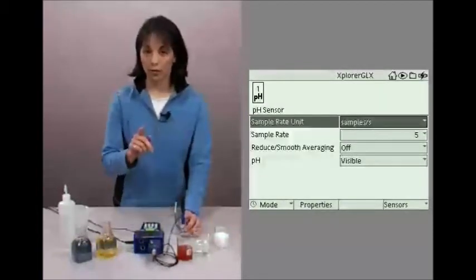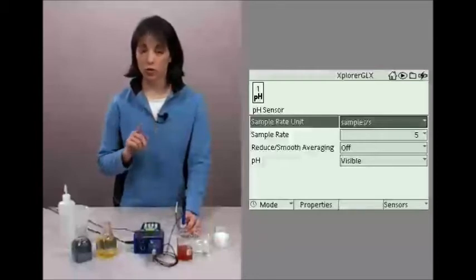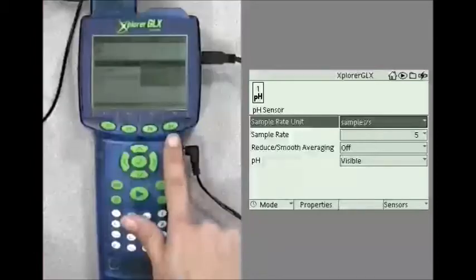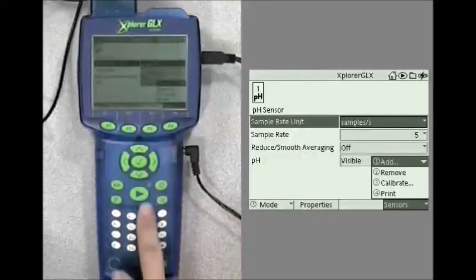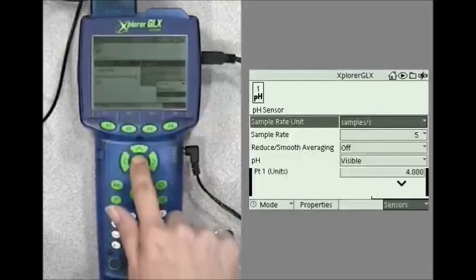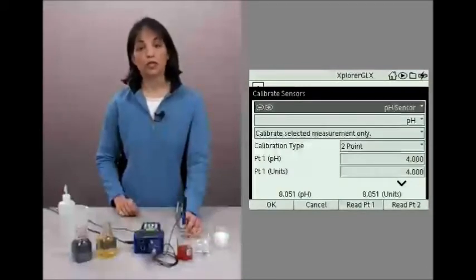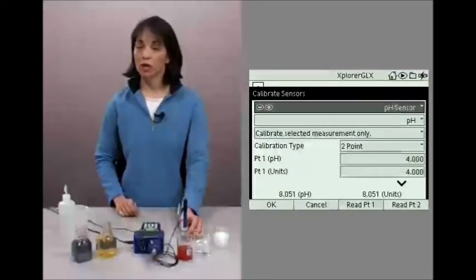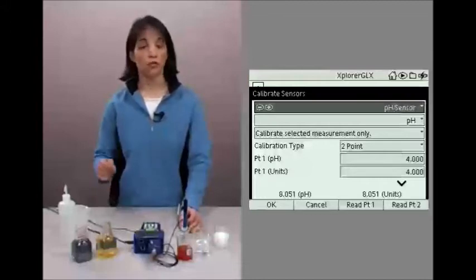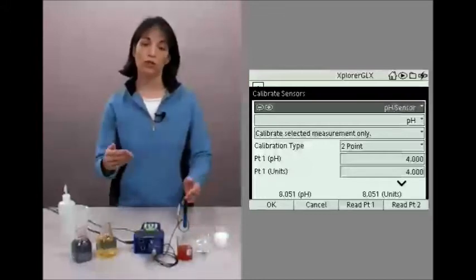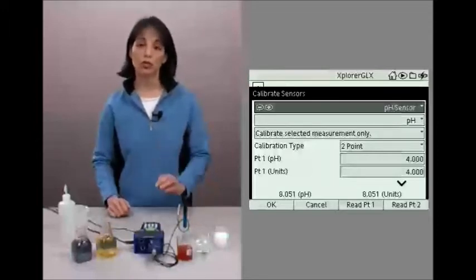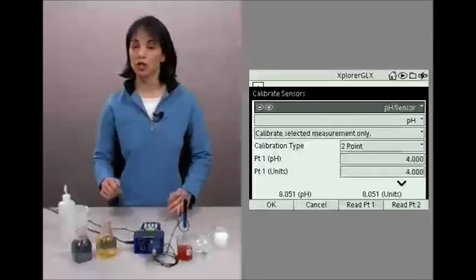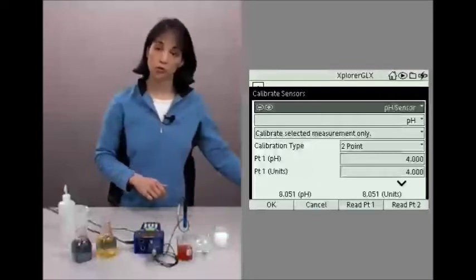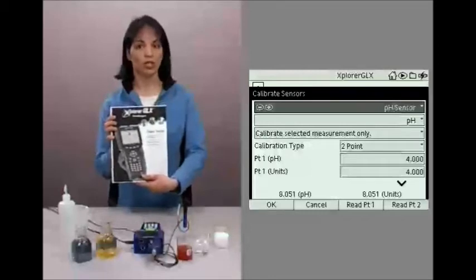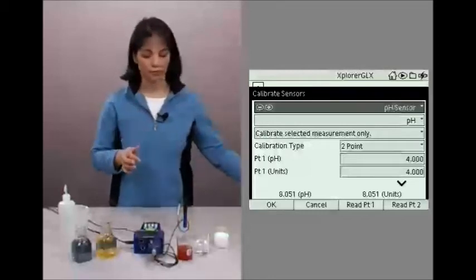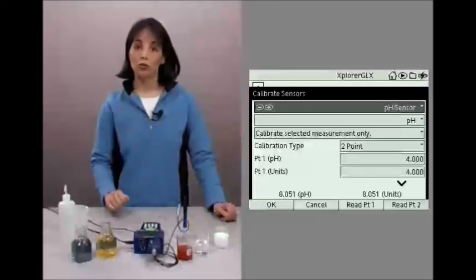Okay, to calibrate, we need to get to the calibration screen, which you do through the sensors menu. So push the F4 button to open that, and you see item 3 there is calibrate. Let's select it. The Xplorer GLX offers a variety of ways to calibrate your sensor. Fortunately, it defaults to the most common type of calibration for the sensor that you have connected. If you're interested in learning more about the types of calibrations you can do with your Xplorer GLX, you will want to refer to your Xplorer GLX User's Manual. We are going to do a 2-point calibration.